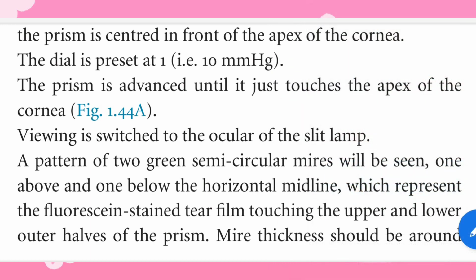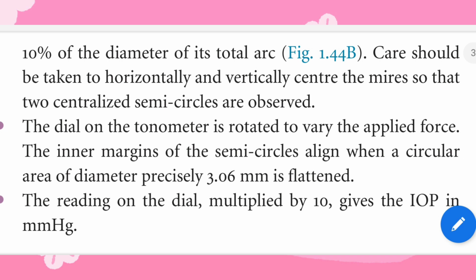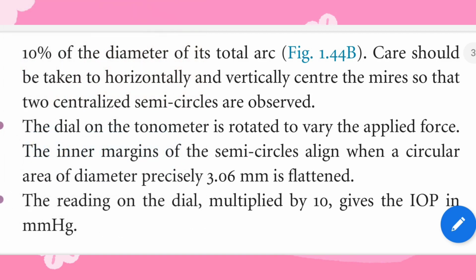Viewing is switched to the ocular of the slit lamp. A pattern of two green semicircular mires will be seen, one above and one below the horizontal midline, which represent the fluorescein-stained tear film touching the upper and lower outer halves of the prism. Mire thickness should be around 10% of the diameter of its total arc (Fig. 1.44b). Care should be taken to horizontally and vertically center the mires so that two centralized semicircles are observed. The dial on the tonometer is rotated to vary the applied force. The inner margins of the semicircles align when a circular area of diameter precisely 3.06 mm is flattened. The reading on the dial, multiplied by 10, gives the IOP in mmHg.